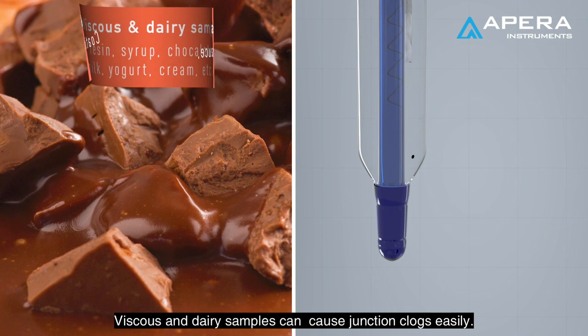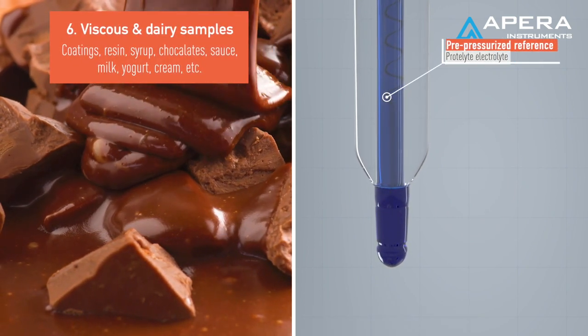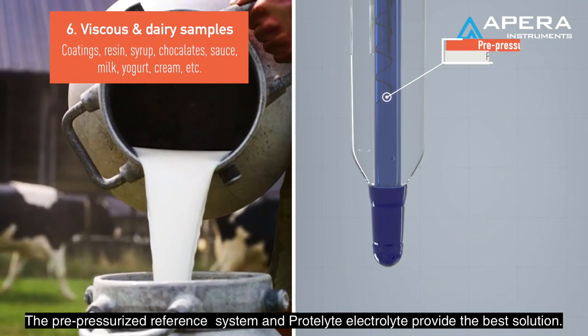Viscous and dairy samples can cause junction clogs easily. The pre-pressurized reference system and Protelyte electrolyte provide the best solution.